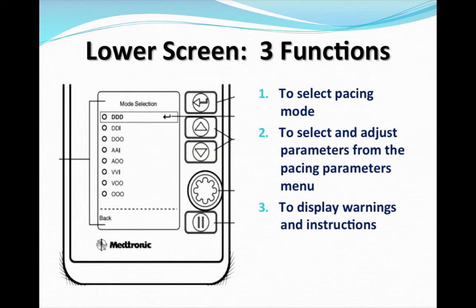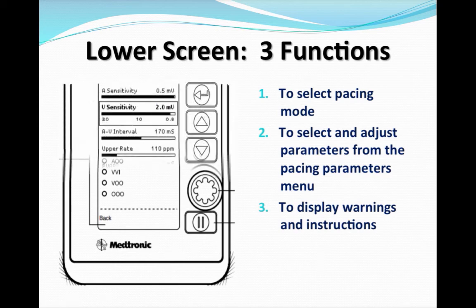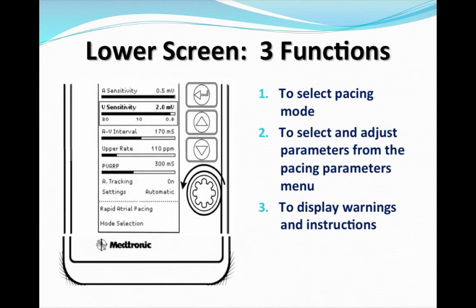The lower screen has three different functions: selecting the pacing mode (DDD, DDI, VVI, and others), selecting and adjusting parameters from the pacing parameters menu such as sensitivity, and displaying warnings like a lock indicator.